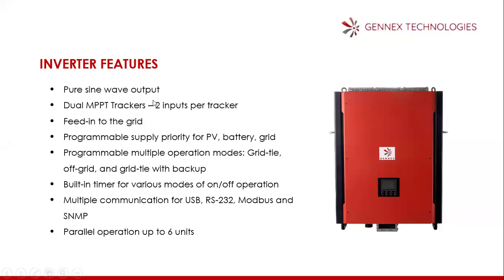It's also programmable for supply priority: PV, battery or grid. So you can program which one you want to be the priority number one. Is it the PV? Is it the battery? Is it the grid? It's also programmable for multiple operation modes: grid tie, off grid, and grid tie with backup. So you can use it as an off grid system, or as a grid tie, which is pushing to the grid, which is not really functioning like I mentioned. Then the grid tie with backup is what we mostly use, which many people are conversant with.